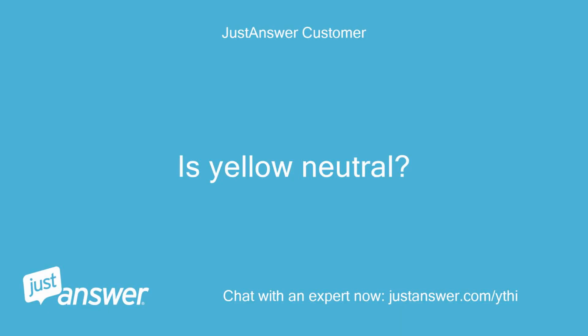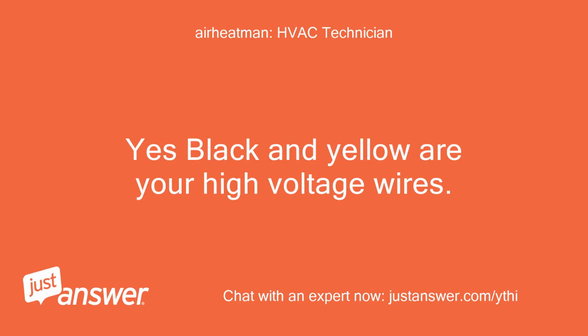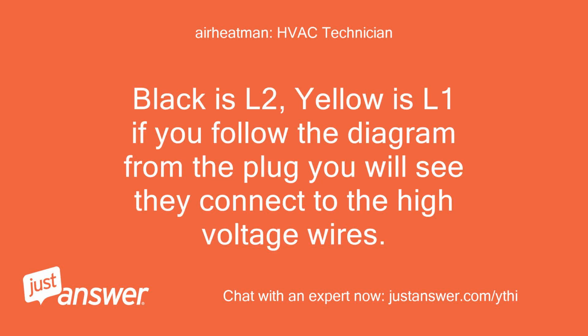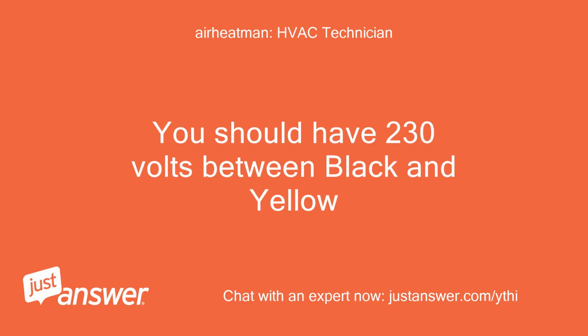Is yellow neutral? Yes, black and yellow are your high voltage wires. Black is L2, yellow is L1. If you follow the diagram from the plug, you will see they connect to the high voltage wires. You should have 230 volts between black and yellow.